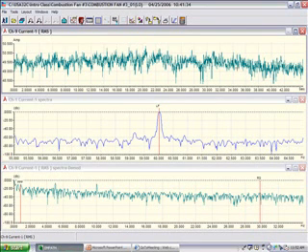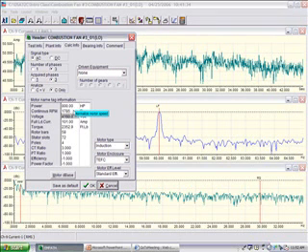This is the current draw during operation. This is, of course, an 800 horsepower, 1785 RPM, 4160 volt, 100 amp motor. With that first one that failed, we were able to actually count the number of rotor bars, which were 58, and the number of stator slots, which were 72.